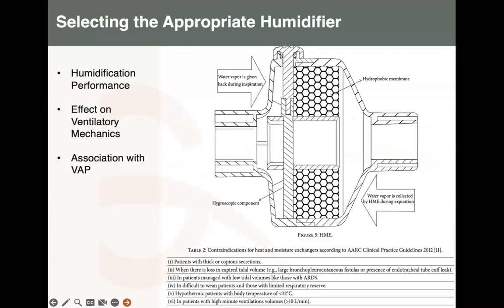One category to look at is the humidification performance of the device. For example, heated humidifiers should provide an absolute humidity level of between 33 and 44 milligrams of water per liter, while HMEs should provide a minimum of 30 milligrams of water per liter. So you can see how the performance works in those two types of devices.